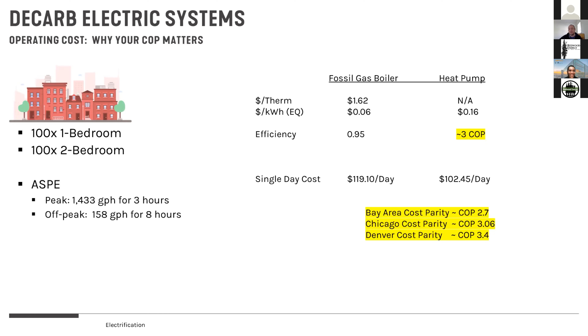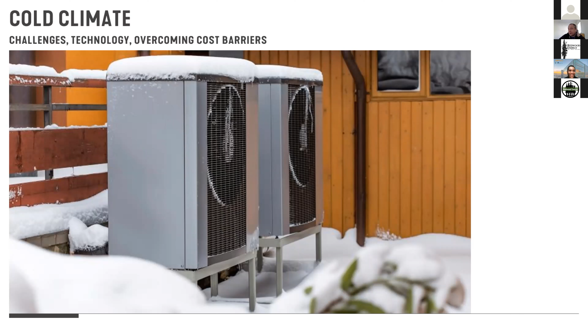So I go to these cold climates and we're like, rah, rah, rah, VRF, air source heat pumps, they're our friends. But when you start to look at the performance curves for most air source refrigeration equipment, you're going to start to see a trend, and it gets pretty severe. It's both dependent on what temperature water I'm trying to make for the building, but it's also heavily dependent on outside air temperature. So you can see as I move towards the left, I get colder and colder. The COP of the system, and this is just the core heat pump itself, is dropping off significantly. If I go past 40 degrees, even lower, like Kip mentioned, we're going to see COPs that are approaching 1.